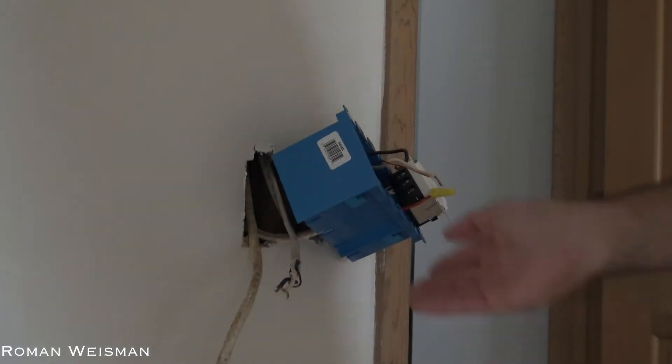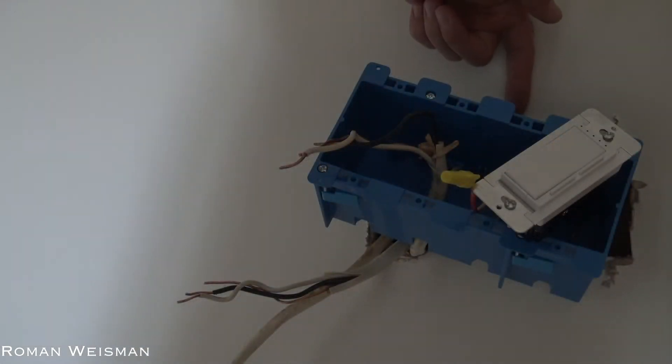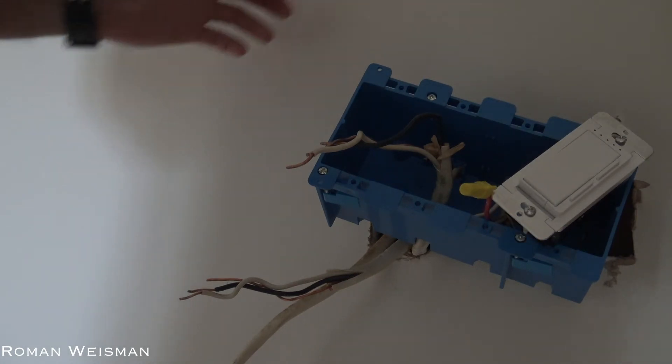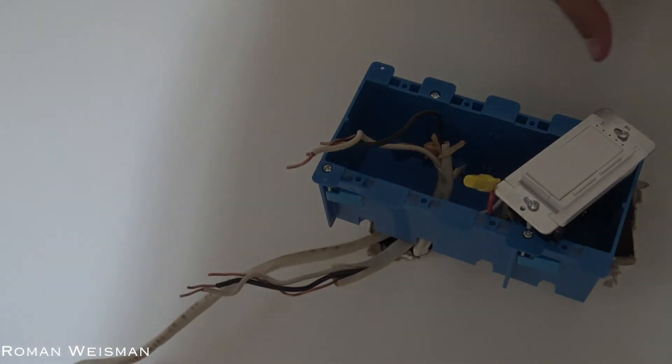Now that I found what's going on here, let me show you one main cable that is coming from the breaker box. And then the rest cables are just an intersection. This one goes to the ceiling. This one goes to the outlet. This one is going to the switch. I was able to find the main one by first disconnecting all this mess, separating them, making sure that the cables are not touching each other. And then turning on the switch on the breaker box and checking with the special instrument where I have electricity. And I had only one cable.